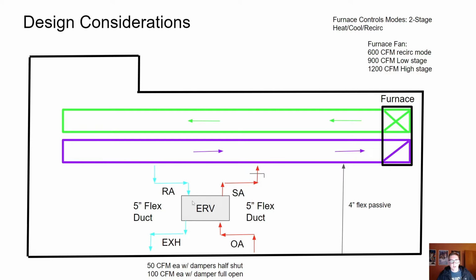And then in your heat exchanger that's inside the ERV, your outdoor air comes in, and the energy from the return air is transferred to the outdoor air. So your supply air is now preconditioned before it goes into the furnace, so you don't have to use either your heating coil of your furnace if you're in heating, or your cooling coil if you're in cooling. And then that return air, once that energy is extracted from it, is exhausted.